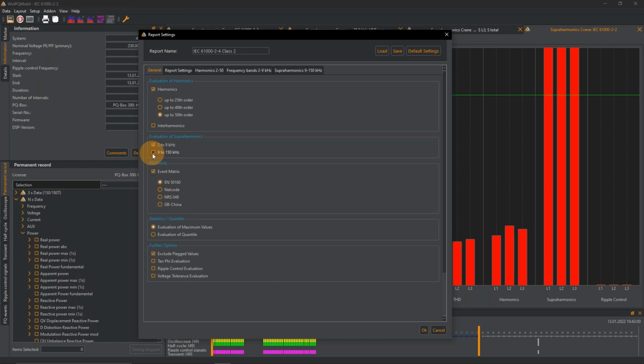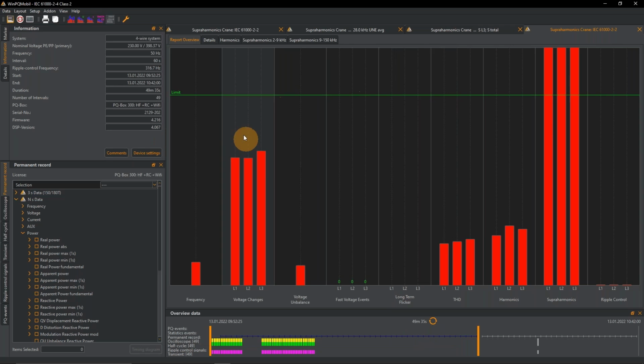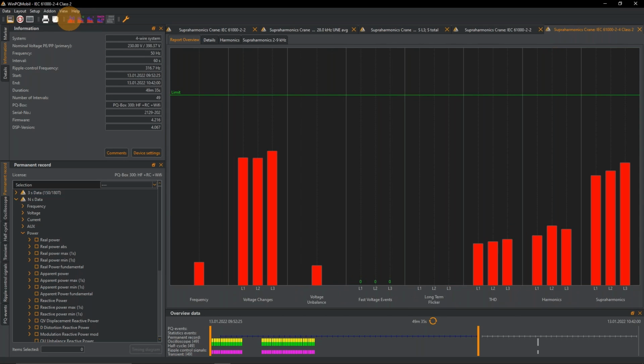It's from 2003, and it only covers limit values for harmonics up to the 50th order. And it gives recommendations, so only recommendations for superharmonics from 2 up to 9 kilohertz. So of course we included these recommendations because any recommendation is better than nothing. So I just click on OK, and now I can simply do a re-evaluation, clicking by that, and voila, everything is fine. No superharmonics, no problem, everything is fine.